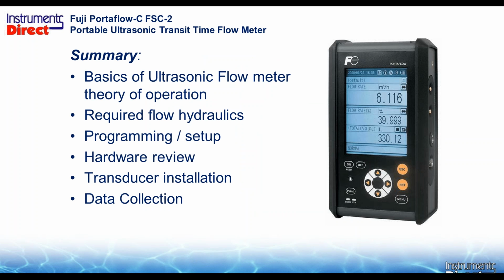So, talked too much as usual. What did we learn today? The basics of ultrasonic flow meters and how they work. In addition to that, we do require some flow hydraulics to make it work better. It doesn't always exist, and sometimes you're in the field and you have to do what you have to do. So if you don't have enough straight run of pipe, you go downstream about 2/3 of the available straight run of pipe and put your sensor there. That's the best you can do under those particular situations.